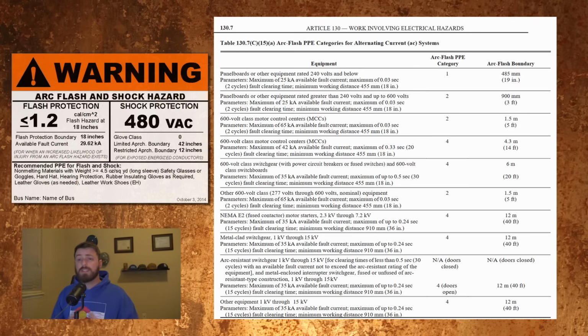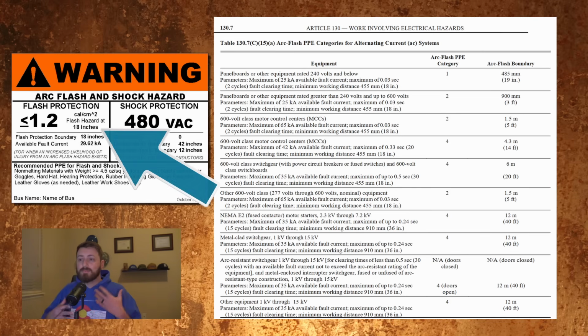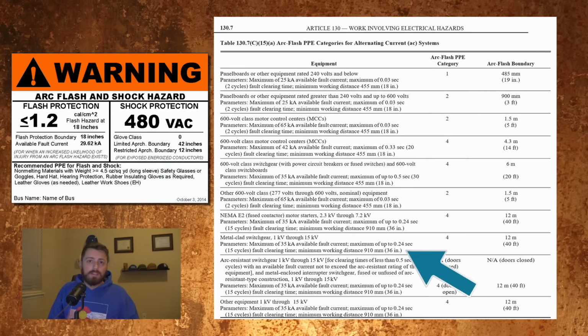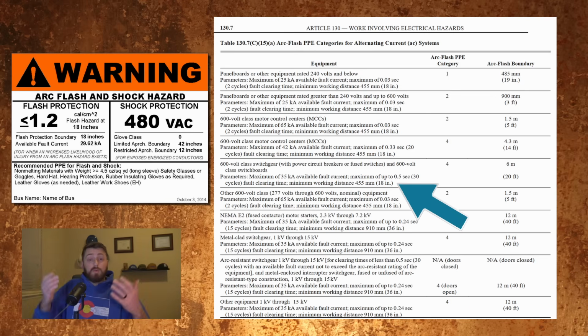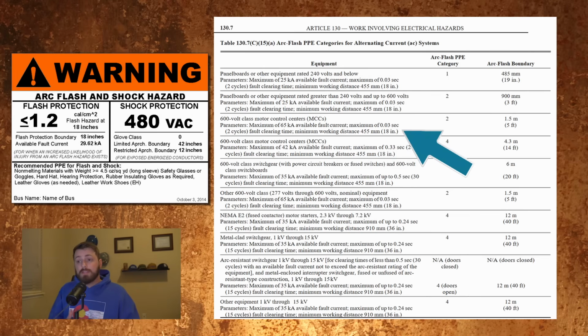Site-specific arc flash studies tend to be more accurate with these assumptions and will state the working distance based on what's physically installed. Some switchgear has a working distance of 36 inches. Some of it's 24 inches. For medium voltage gear, it could be even more than that. Most switchboards are a 24-inch working distance. Some are 18. It really depends on how large the breakers are and how far your face will be from hot components. In general, panelboards and MCCs have a working distance of about 18 inches.